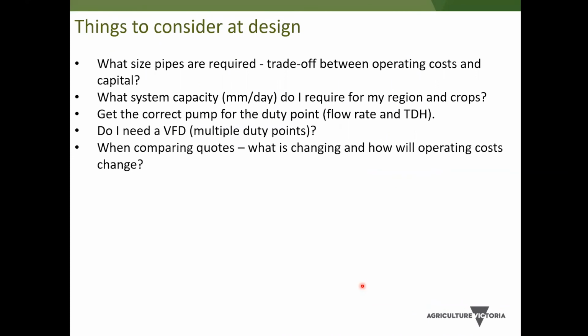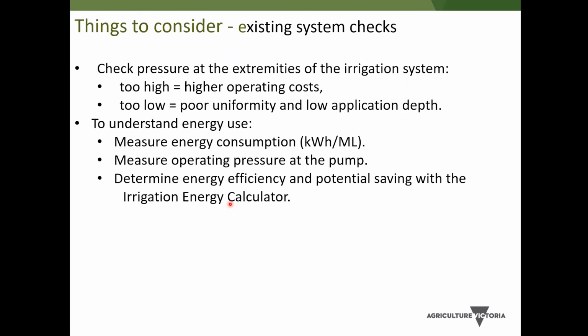So finally, things to consider at the design phase. What pipe sizes do we require? There's always that trade-off between operating and capital costs. What system capacity do we require for our area? And make sure we've got a pump that matches the duty point of our irrigation system. Do I need a variable frequency drive? Well, that'll depend on whether we've got multiple duty points or not. And when we're comparing quotes, make sure we understand what different suppliers are charging and what impact that's going to have on overall pumping costs.